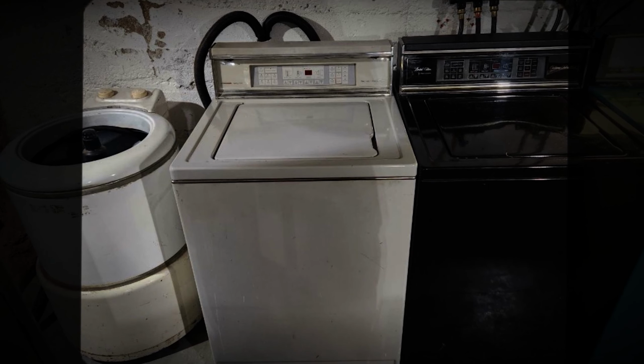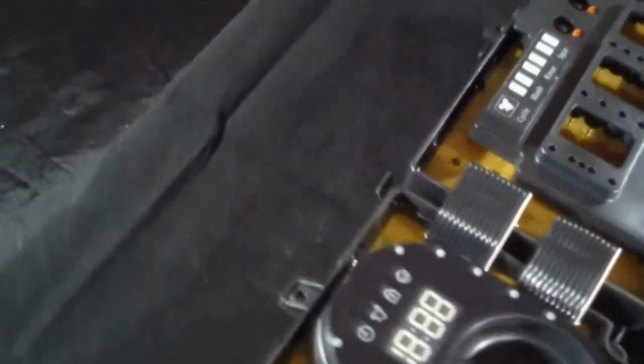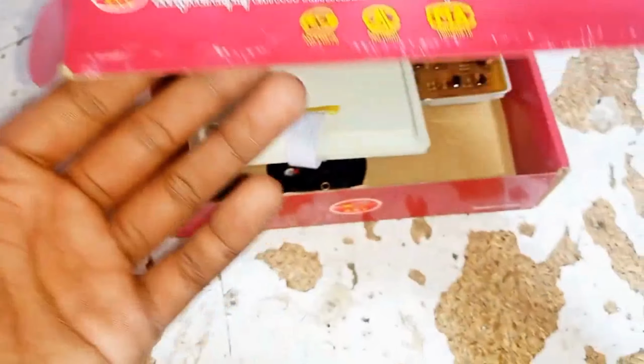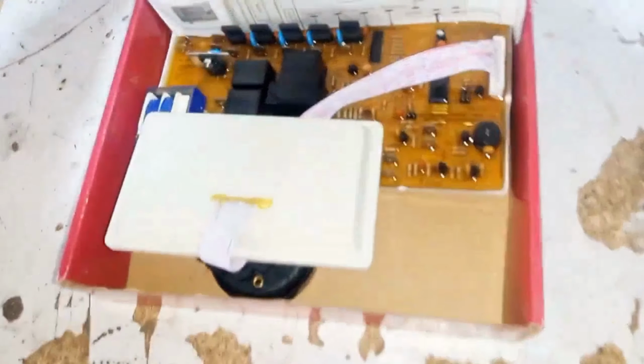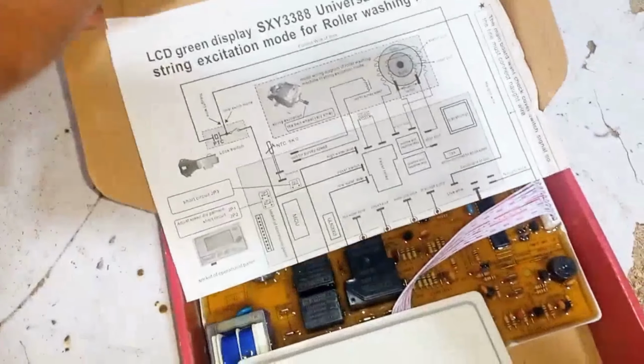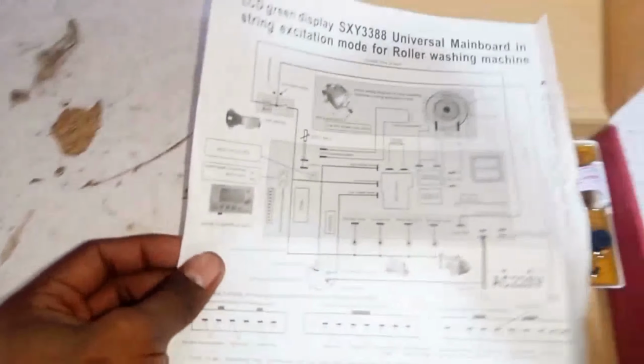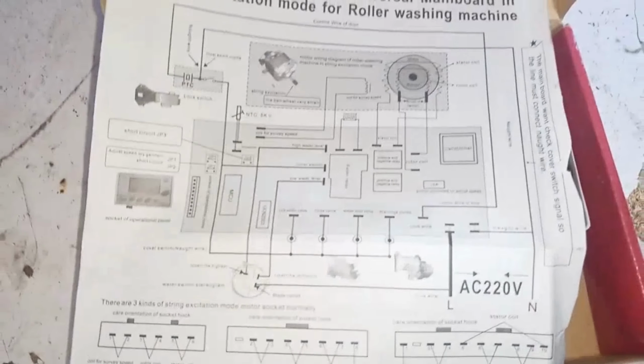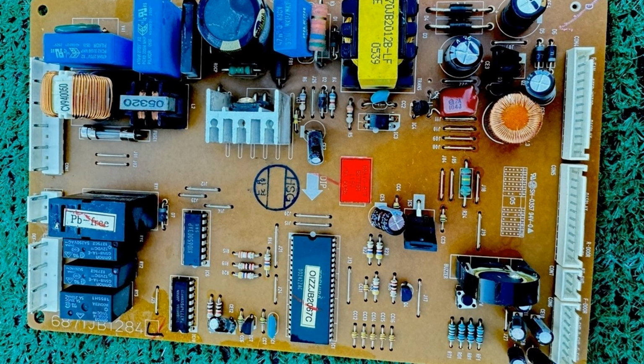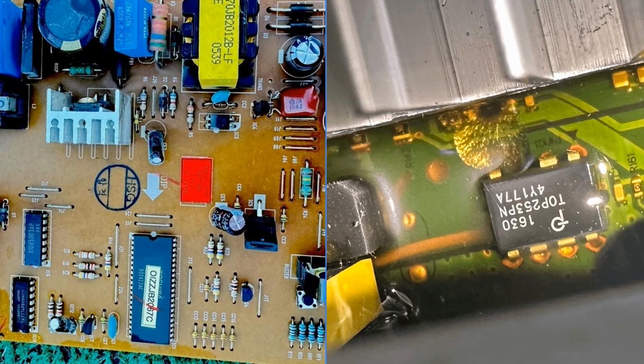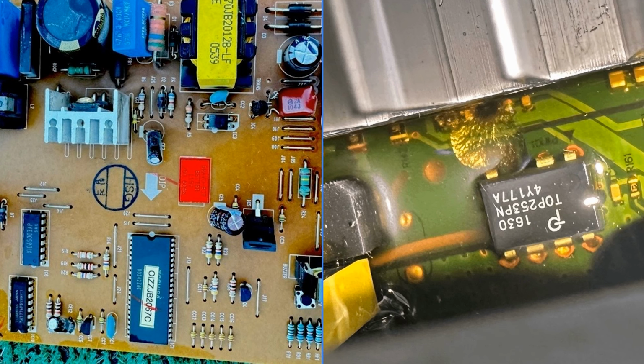The board itself is also serialized to the machine's firmware. If you find a third-party CCU on the aftermarket, the AliExpress clones that run $50 to $100, there is a documented risk that the replacement board creates new error codes because it does not carry the original machine's calibration data. Proprietary firmware recognizes OEM components versus aftermarket components and responds accordingly.